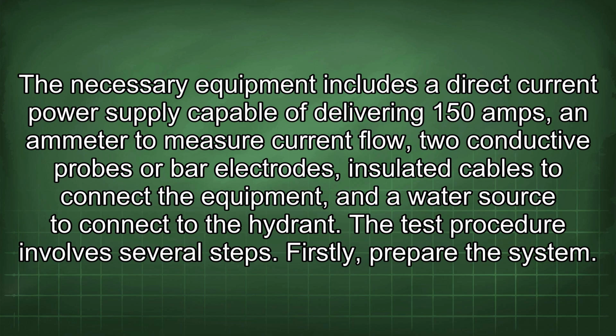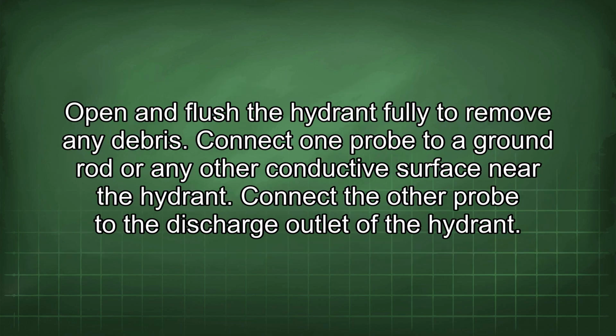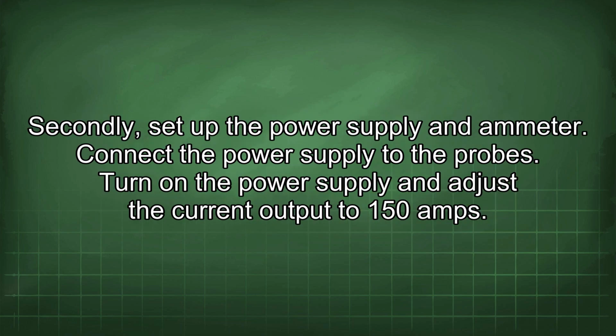Firstly, prepare the system. Open and flush the hydrant fully to remove any debris. Connect one probe to a ground rod or any other conductive surface near the hydrant. Connect the other probe to the discharge outlet of the hydrant. Secondly, set up the power supply and ammeter. Connect the power supply to the probes.